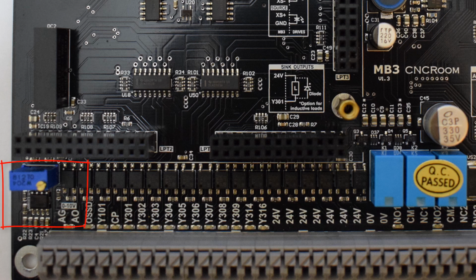And last of all, down in the corner here, we've got the AnaSpeed 2 circuit. The AnaSpeed 2 circuit actually has its own DC to DC power supply, so it's supplying its voltage to it. It's isolated from the rest of the board, and it will not suffer from any voltage spikes, any rising or lowering. So the speed you set will always be a constant voltage going to the VFD.